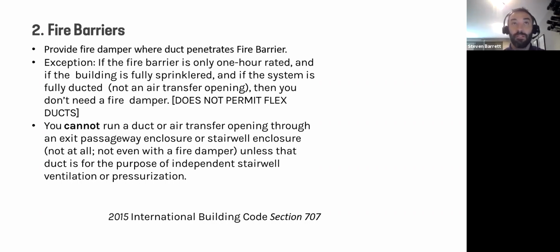Another important note is that you cannot run ducts or air transfer openings through exit passageways or stairwell enclosures. Period. Not at all. You can't do it unless those are specifically serving the stair. So you cannot utilize stairs or exit passageways as pass-throughs for your ductwork. So again, on that exception, important to note, it will not apply for air transfer openings and requires a fully ducted system, no flex.